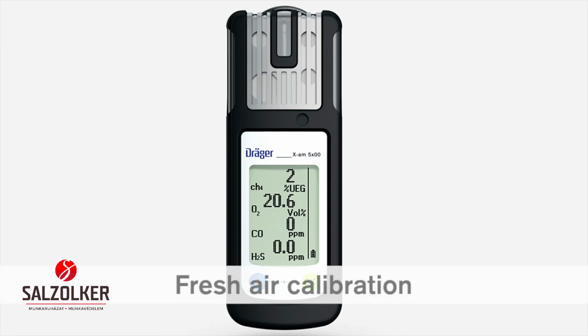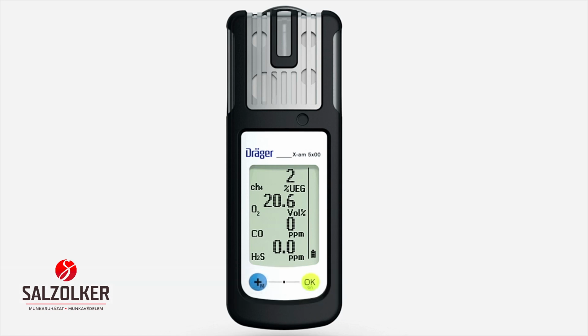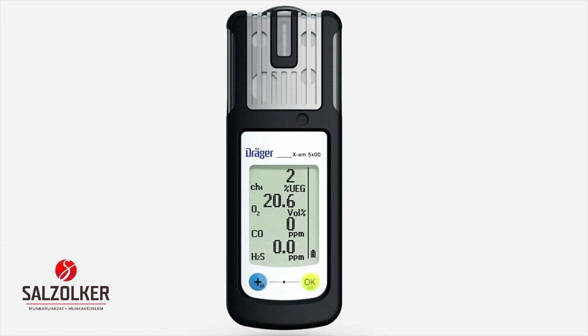You can use the fresh air calibration function to set the oxygen channel to 20.9% by volume and the other sensors to 0. Make sure that you are in an area with clean air when you perform the fresh air calibration. The following additionally applies for the Dräger X-am 5600. The fresh air calibration and zero adjustment are not supported by the Dräger sensor Dual IR-CO2, Dräger sensor IR-CO2 or Dräger sensor XXS-O3. A zero adjustment of these sensors can be conducted using the Dräger CC Vision PC software. To do so, use a suitable zero gas that is free of carbon dioxide and ozone, for instance nitrogen.